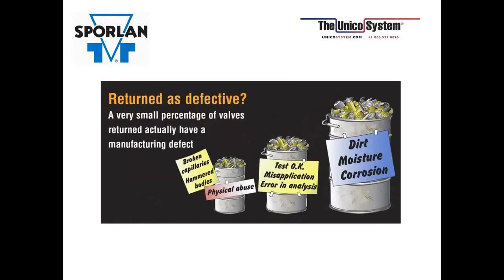This is a great slide, guys. I really was impressed when I saw this. So, especially you guys on the wholesale side, I think you'll find this to be quite interesting, what they get back when they analyze the returns. We get lots of valves back that just say they're defective. Defective doesn't necessarily mean that the valve is bad in this case, because a very small percentage of valves returned actually have a manufacturing defect. And these barrels are relative to the number of valves we get back and the actual cause of those valves being returned. Most of them we find in a small barrel with broken capillaries and some kind of physical abuse, hammered body type thing. The middle barrel, all the valves test out okay. It's either been misapplied or there's been an error in analysis by the technician.